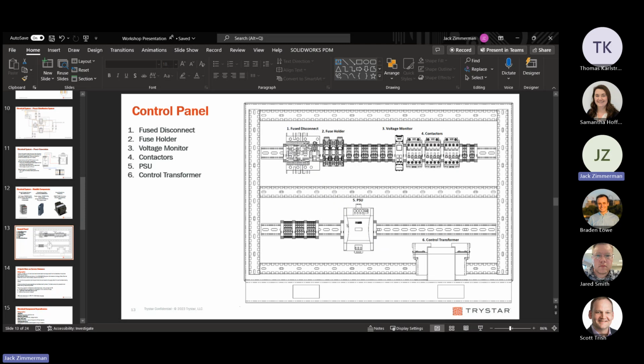The only point where you'll have active voltage in this box is on the top side of your disconnect, because it's coming from utility. So this is the only point. Everything downstream would not be energized. Of course, you have to go through the process.